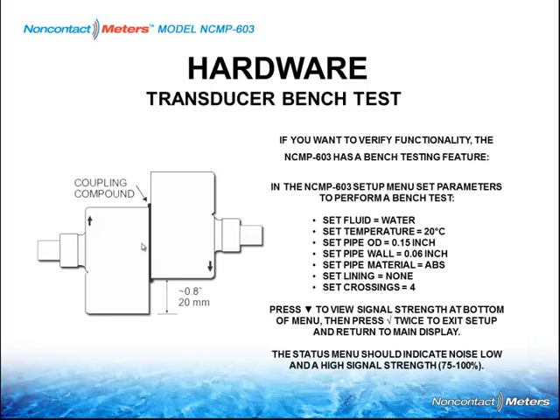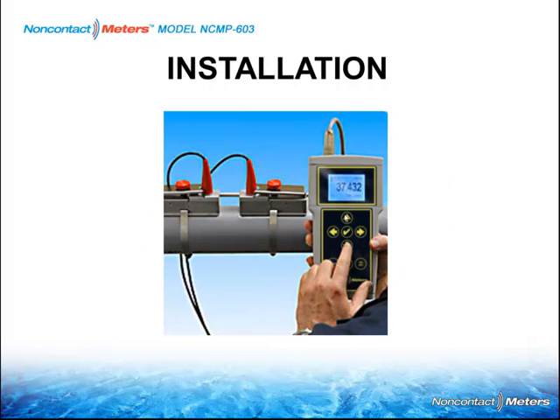It's pretty cool. Here's a picture of the installation we were talking about. We have these stirrups here, and the stainless steel clamps, and basically this little alligator clip here, and the transducers pop in and out over here. Do note, versus other transit time flow meters, in this particular design the cables are on the inside. Everybody else has their cables pointing on the outside. So, different technology there. As you can see, this picture is actually wrong in that it's at 12 o'clock. We prefer not to put the sensors at the top of the pipe.